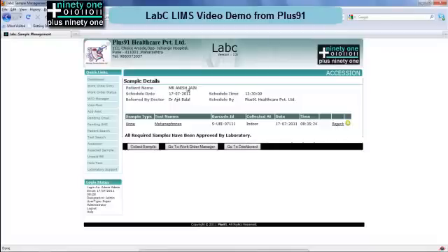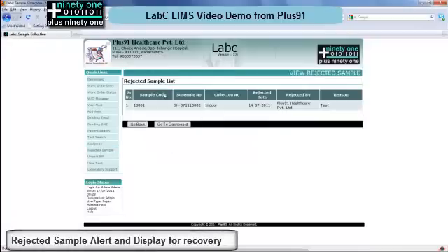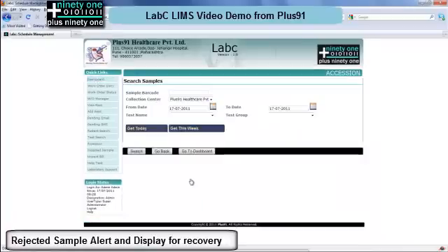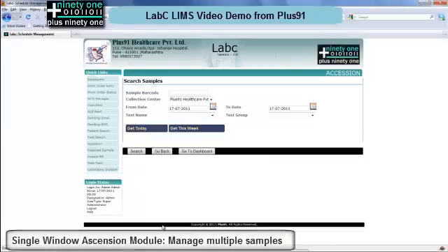Click on the reject button, enter the reason and the sample will be rejected. After this the test will not go ahead without a new sample being collected — this again follows the NABL guideline. You can get a rejected sample list and also alerts can be created via SMS or display alerts to take things forward.